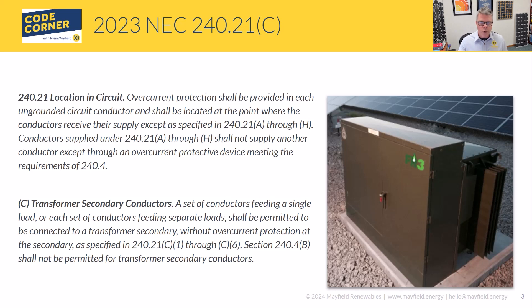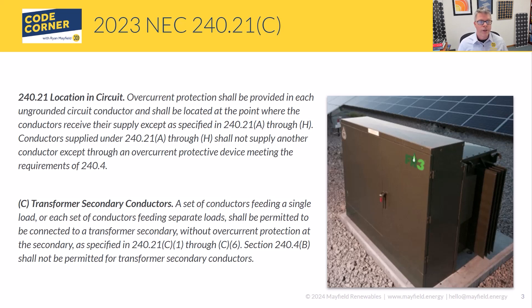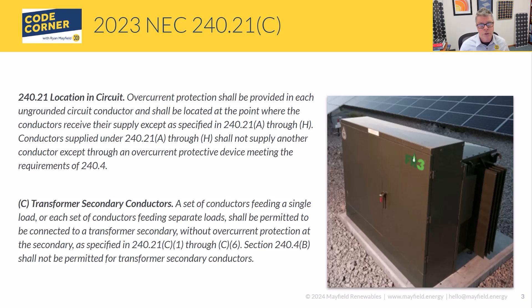240.21 is the location for overcurrent devices. Part A talks about branch circuit conductors, B talks about feeder taps — which is a common application for our interconnection methods covered in 705.12. Part C is talking about transformer secondary conductors. What this section says is that the protection doesn't necessarily have to be right at the transformer itself — similar to what we do with taps, we can have some distance before the overcurrent protection device, and we have to meet the requirements of C1 through C6.